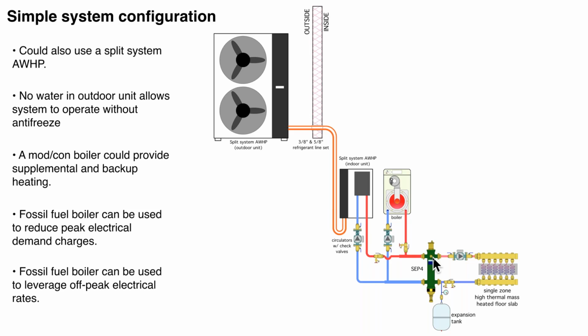Now, how you control these two heat sources, there are a lot of possibilities. The basic one would be to let the heat pump be the primary heat source, so that would be fixed lead stage heat input. The controller would watch the supply temperature going to the floor. If the heat pump is unable to keep the actual measured temperature close to the target, it would bring the boiler on. That's just a typical two-stage heat input controller. There are several of them on the market. But it also opens up the possibility that we could use the heat pump during off-peak hours where we have lower electrical rates, and then switch to the boiler during peak time.